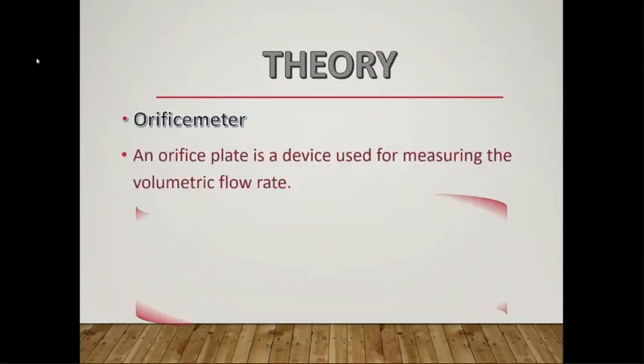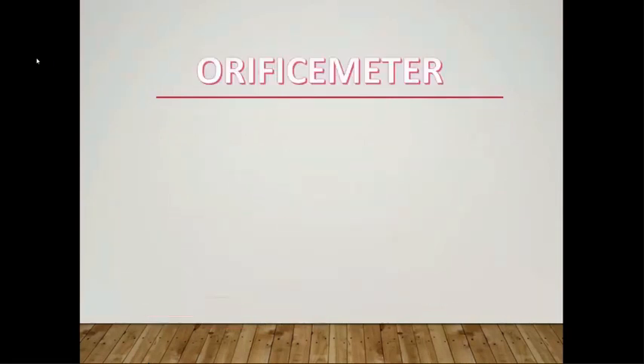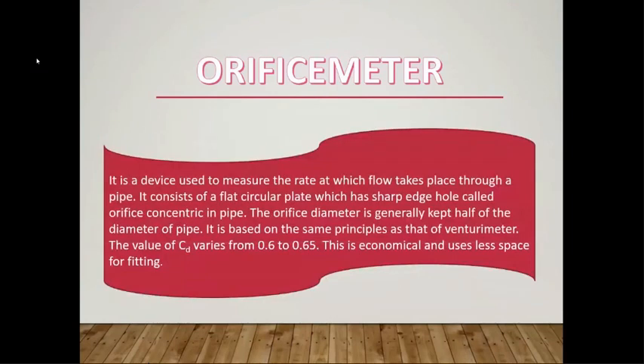The orifice meter uses the same principle as the venturi nozzle, namely Bernoulli's principle, which states that there is a relationship between the pressure of the fluid and the velocity of the fluid — when velocity increases, pressure decreases and vice versa. The orifice meter is a device used to measure the rate at which flow takes place through a pipe. It consists of a flat circular plate with a sharp-edged hole called an orifice, concentric in the pipe. The orifice diameter is generally kept half the diameter of the pipe.